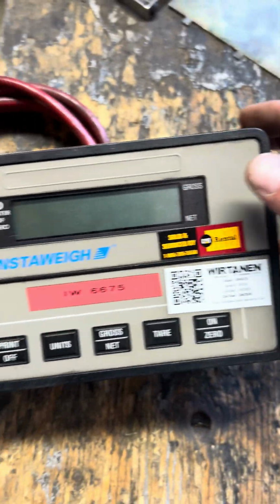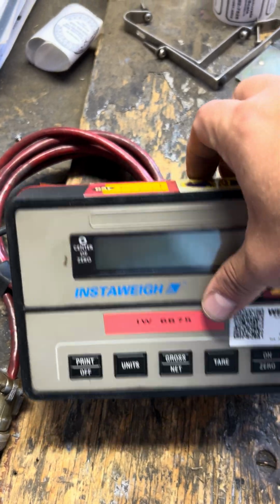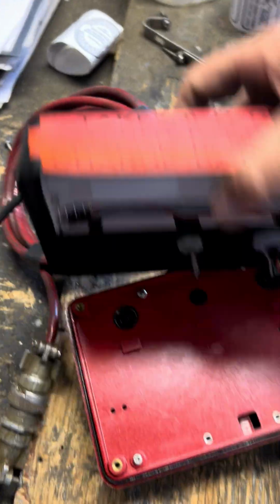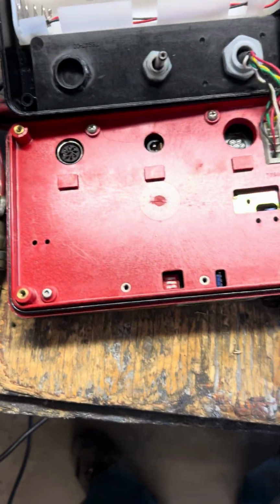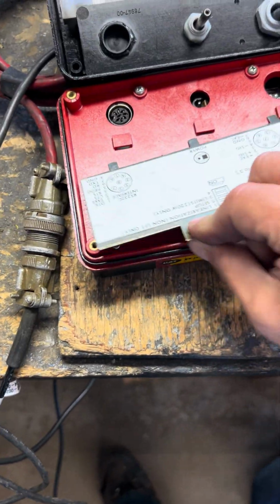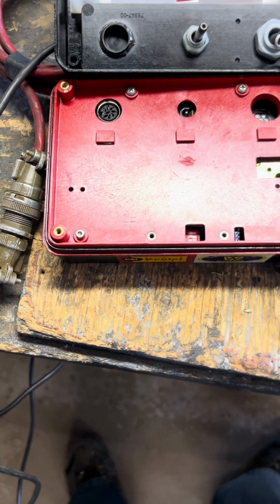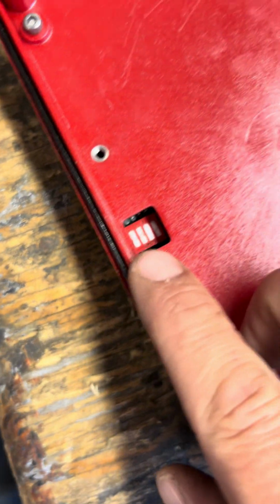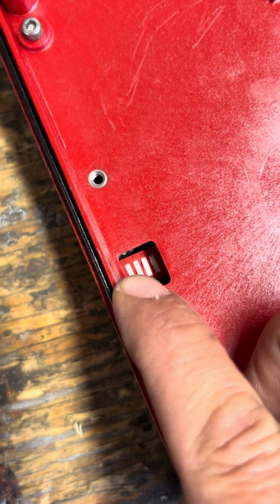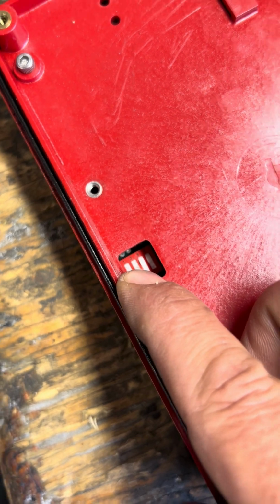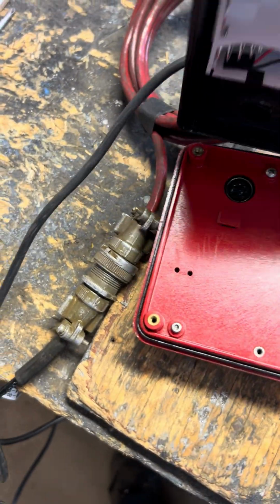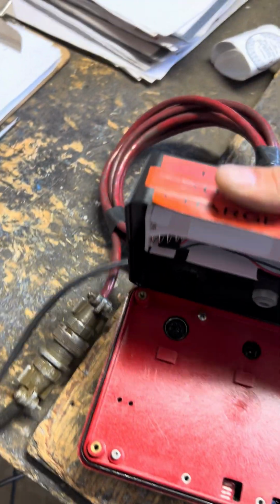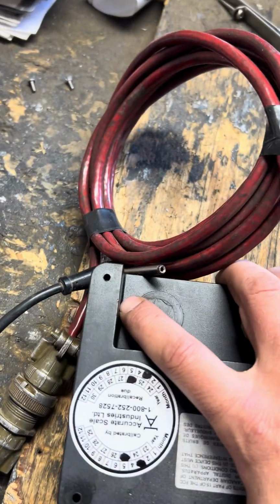To go to the calibration menu, you should open the indicator, unscrew the bolts, and remove the splatter cover. Here you have switches. Switch number 2 should be on to enable the calibration. Then you close the indicator.